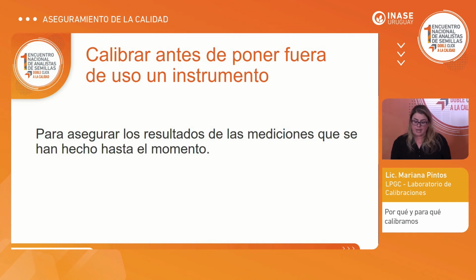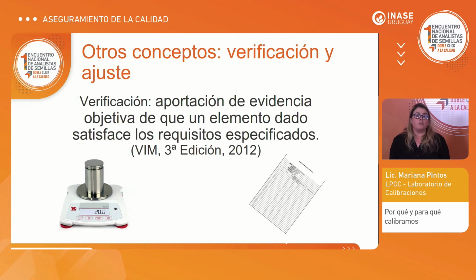What really matters is that before we stop using a piece of equipment, we need to decide what to do with the calibration, because when I calibrate a piece of equipment that I will stop using, it can tell me how accurate this instrument has been over time. And if this happens, then I need to study all the measurements I took with this piece of equipment if it's out of range. So we need to consciously determine the calibration frequencies.